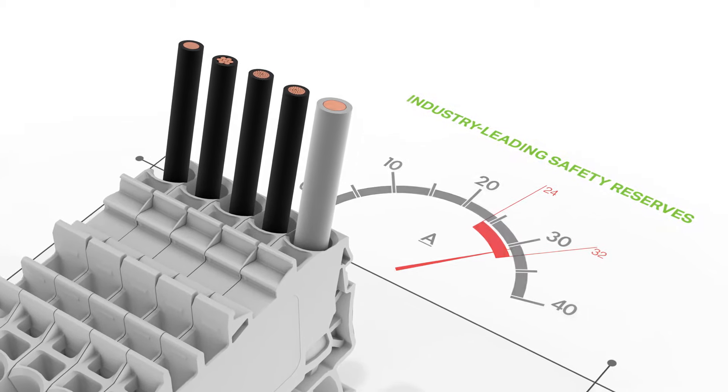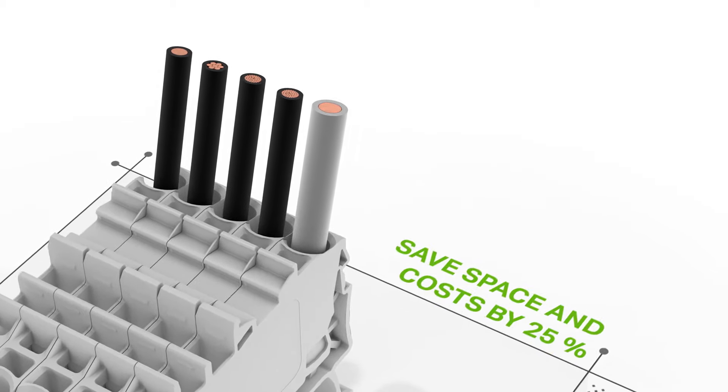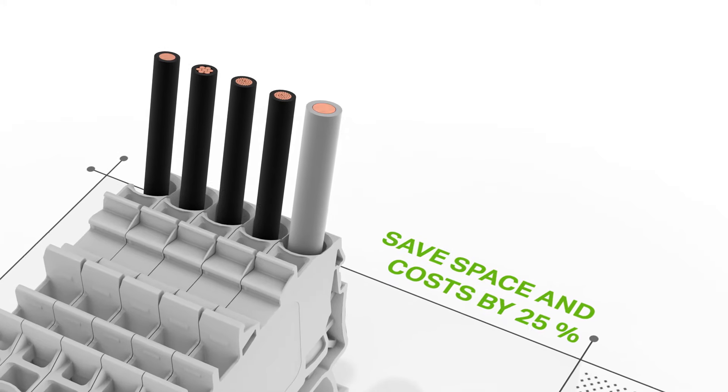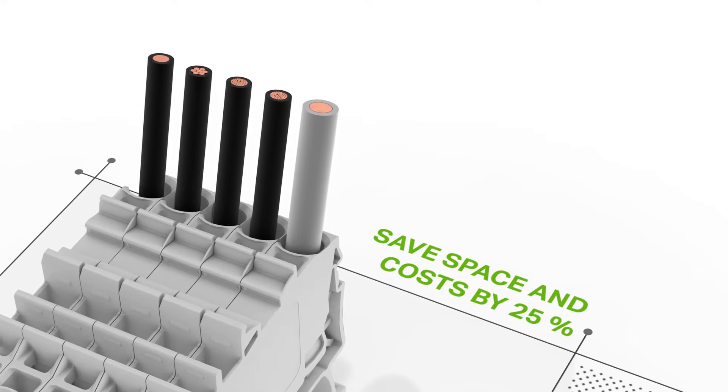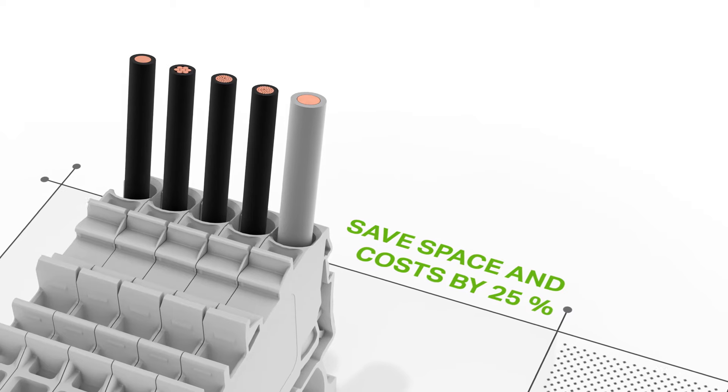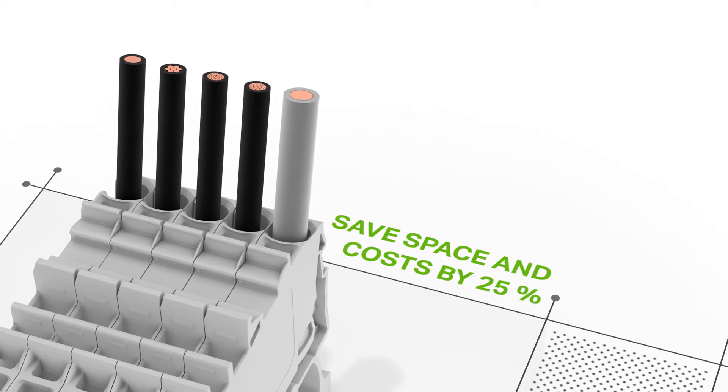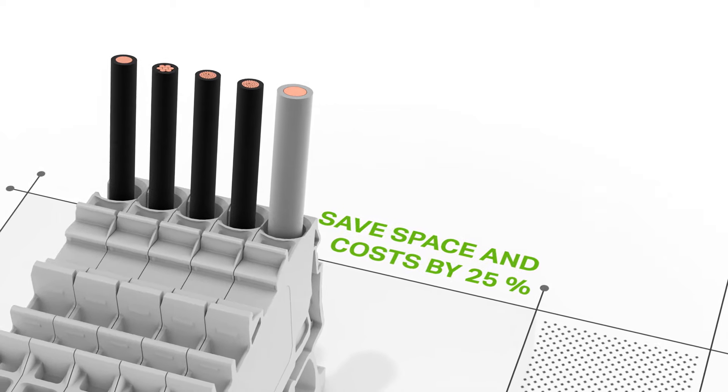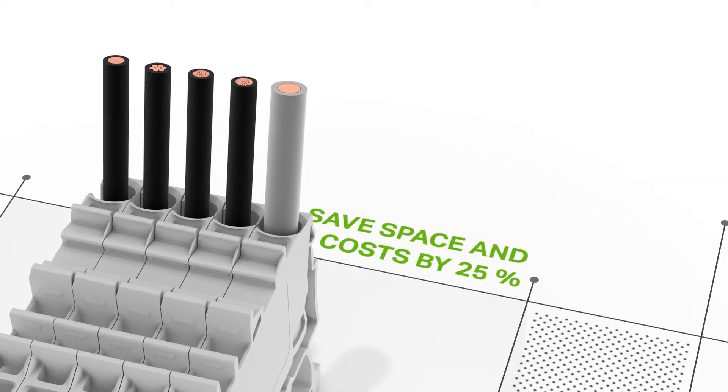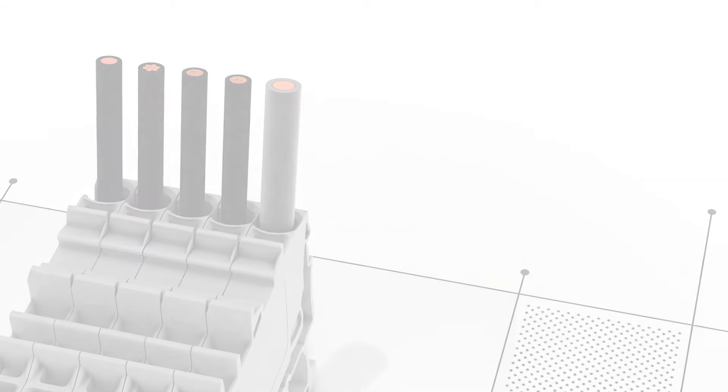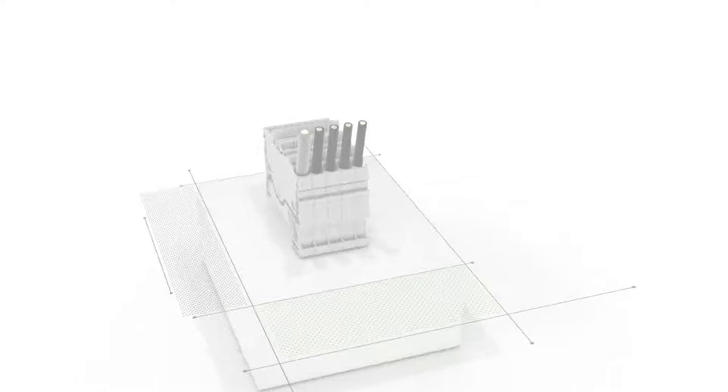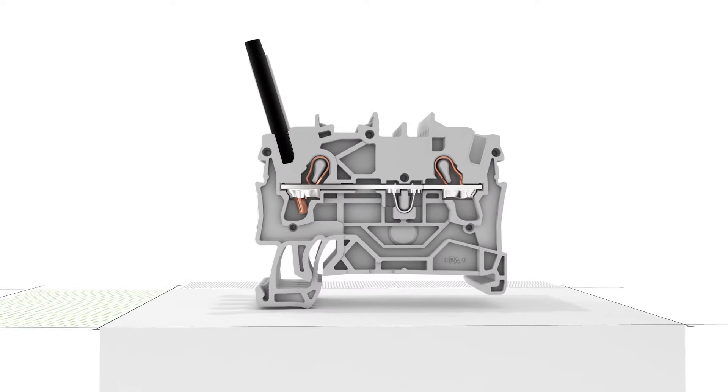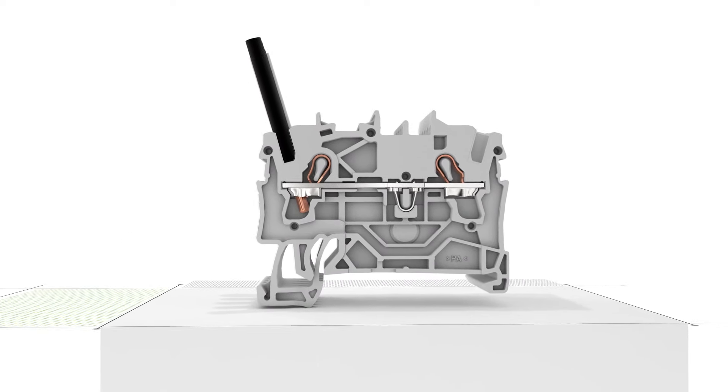Using smaller terminal blocks for larger cross sections and current ratings saves up to 25% more space and money. This advantage provides greater in-the-field wiring flexibility, allowing you to use a 16-square-millimeter terminal block even if the main connection requires a 25-square-millimeter conductor.